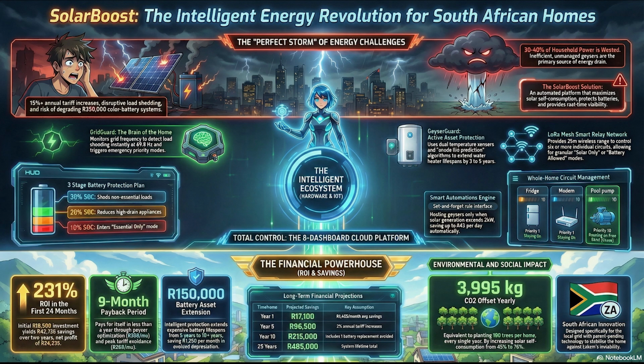The first is solar only. This is a highly restrictive state. It dictates that the appliance will only run if the CT clamps detect the solar panels are actively generating a surplus of power greater than what the house is currently consuming. So it will never pull from the Eskom grid, and it will never, under any circumstances, pull power from the battery. It lives entirely on free excess energy.